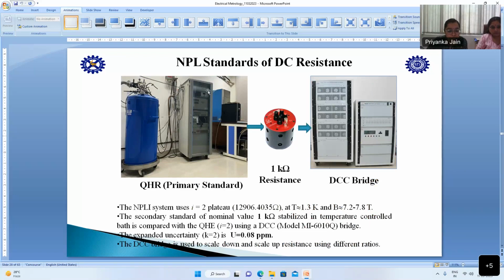And this is our Q10 DCC bridge, that is, direct current comparator bridge. We keep our 1 kilo ohm standard here. We compare this plateau value with respect to this bridge when we arrive at the value of 1 kilo ohm. This 1 kilo ohm standard is the primary standard with an uncertainty of 0.08 ppm. Using this, we deliver, that means we calibrate all other resistance standards using another DCC bridge with the ratio method. So 1:10, 1:100, and 10:1 ratios we have. Based on this, we calibrate our resistance from 10 micro ohms to 1 tera ohm.